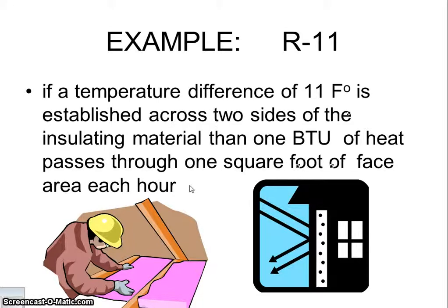What if you wanted to double your R-value to R22? That means your temperature difference would be 22 Fahrenheit degrees for 1 BTU of heat to pass through 1 square foot each hour. The thickness required would double — so for R22 with glass fiber you'd need at least 6.5 inches, and 6 inches of rock wool.